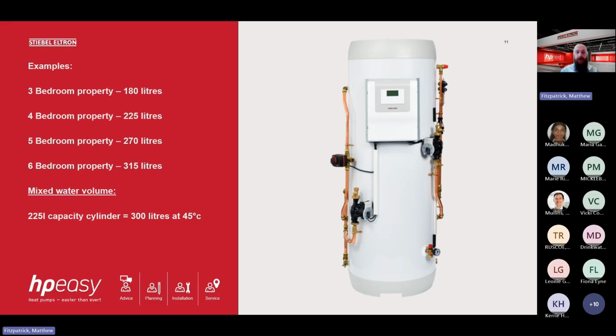So if we take, for example, our 225 litre capacity pre-plumb cylinder, and we held the cylinder at 55 degrees, and we only required a mixed water volume of 45 degrees, then we can achieve 300 litre capacity, which would cover a 3 and 4 bedroom property if it's a single bath and a shower. So it's not always about the size of the cylinder, it's the energy we can get out of the cylinder and how we can modulate it.